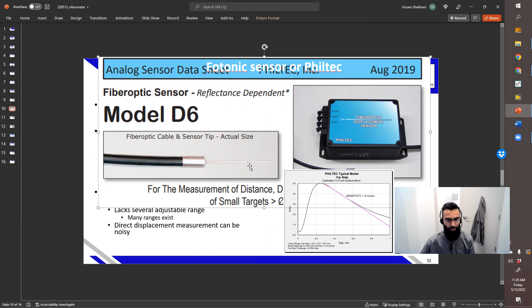However, the biggest differences between this technology and the vibrometer are two. One, I mentioned it's a displacement device, so the closer or farther you get to your target, the voltage reading changes. This is a direct voltage reading, so it's analog—these terminals here are voltage. So this is what happens.